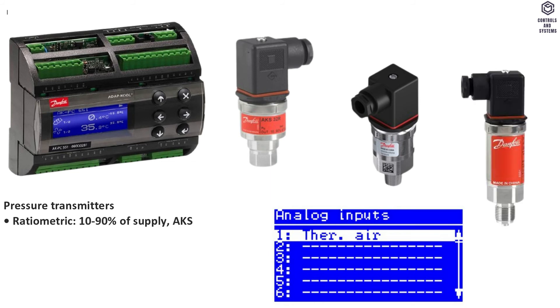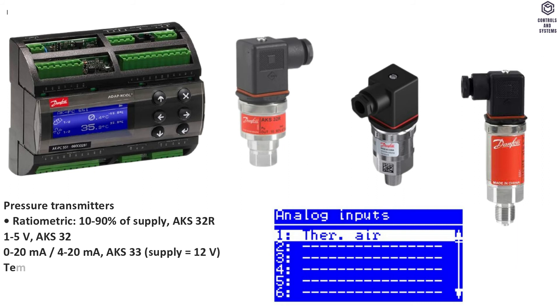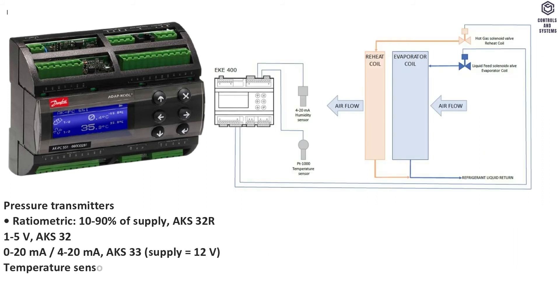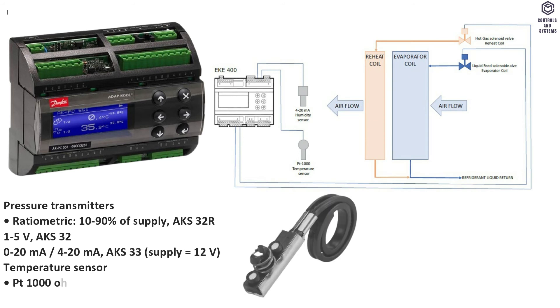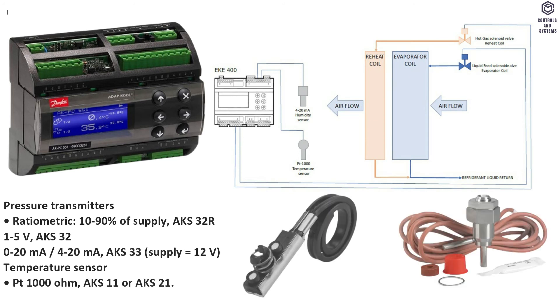Analog inputs — pressure measuring: ratiometric pressure transmitter 10 to 90% of supply, type AKS32R; 1 to 5V pressure transmitter, type AKS32; 0 to 20 or 4 to 20mA pressure transmitter, type AKS33. Temperature measurement: PT1000 ohm (AKS11 or AKS21); NTC 86kΩ at 25°C; and input from digital scroll.